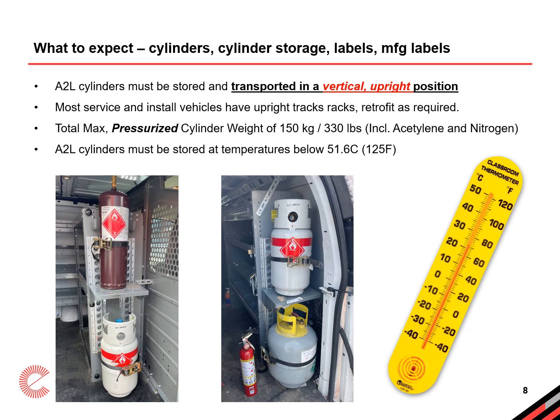Transportation of dangerous goods states that we can operate under the 150 kilogram exemption, thereby allowing a service van or truck to carry up to a total weight of 150 kilograms or 330 pounds of pressurized gas cylinders without the need for any placarding, specialized training, or shipping documents to be carried. That total weight must include the tare weight and the contents of all transported cylinders, like your nitrogen, virgin and recovered refrigerants, and your acetylene.